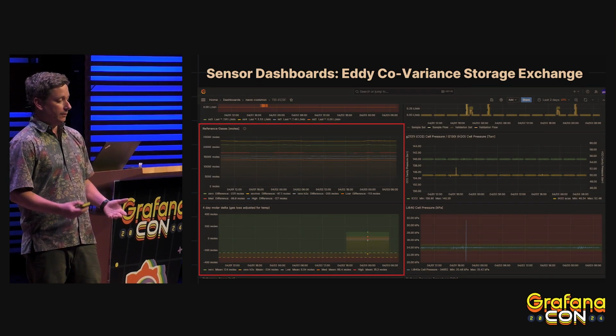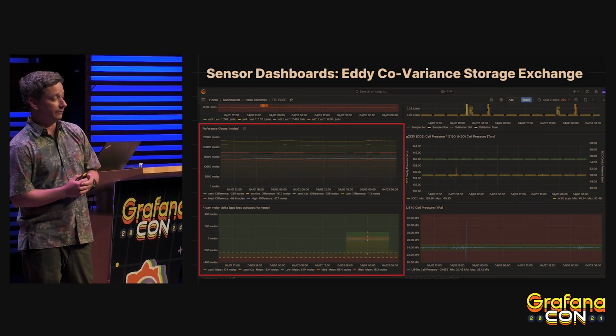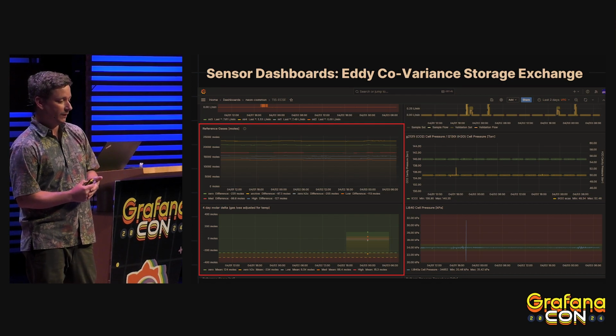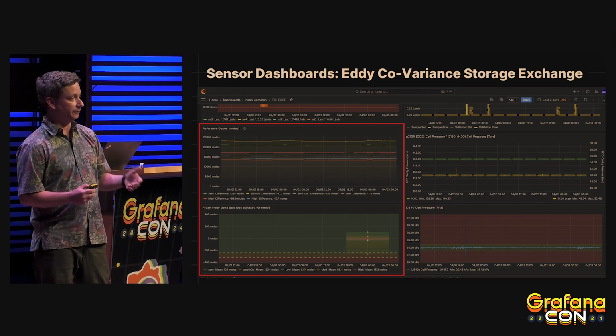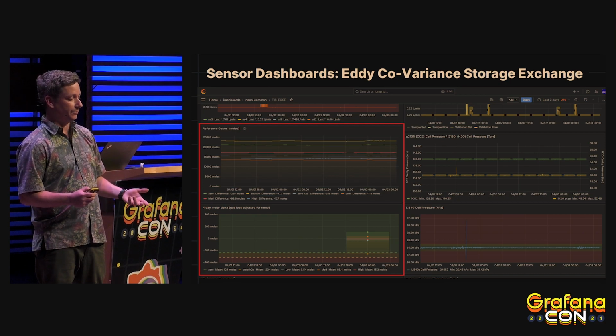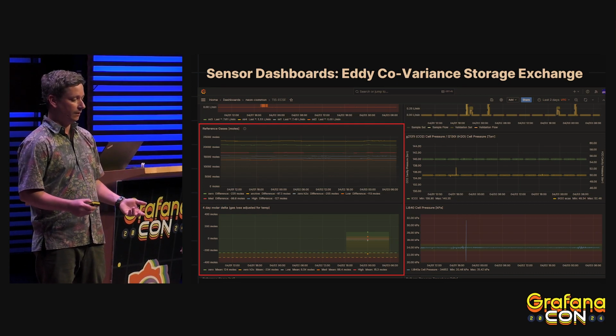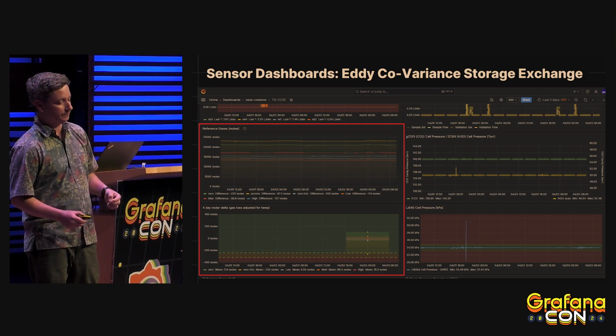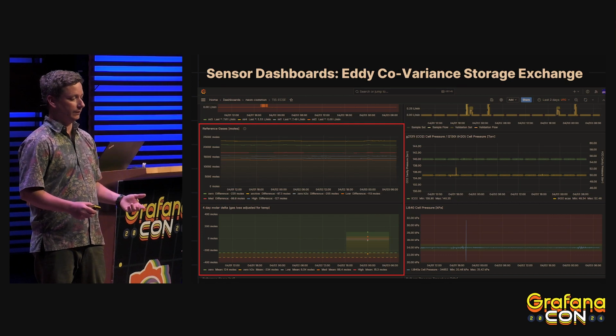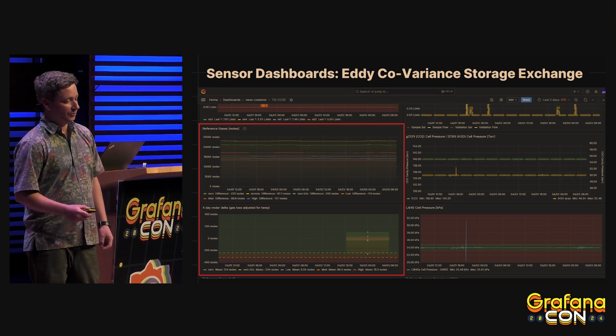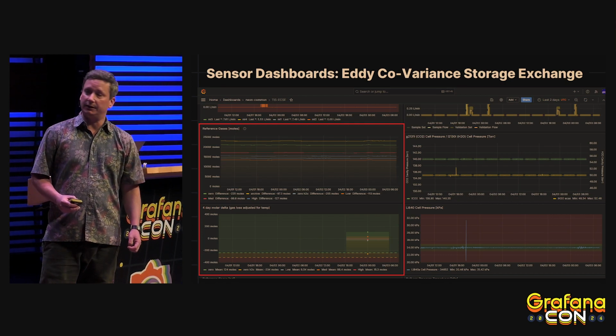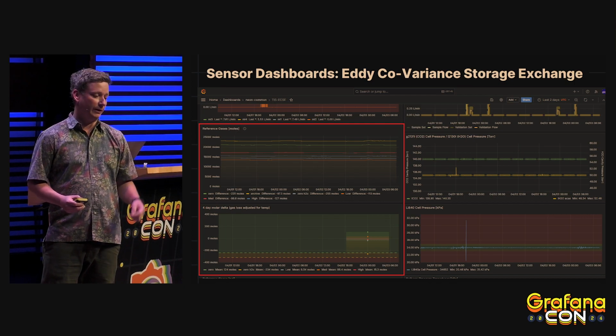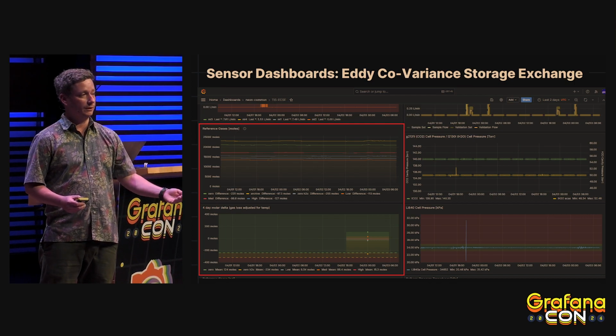Moving down the page, the top panel here shows validation gas depletion over time. We actually have this corrected for fluctuations in temperature throughout the day in real time using an environmental probe and the ideal gas law. We're doing this with a query. It's pretty cool. It makes it a little bit easier to see when leaks are happening. The bottom panel there shows a 4-day delta that highlights if one cylinder might be leaking more than the others over time.